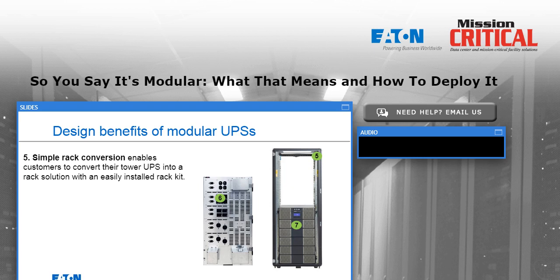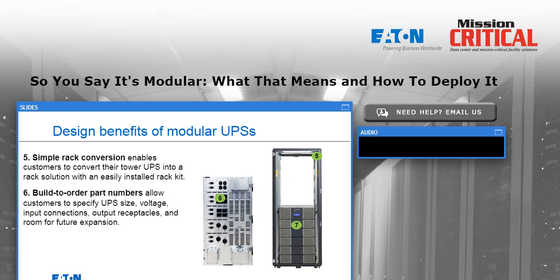If you're choosing to hardwire the output to this UPS, let's say to a panel on the wall or even an RPP, remote power panel, that can be done as well. But the receptacles give the ability to add and change things in the lineup of equipment cabinets without necessarily having to involve an electrician every time I bring in another load to put on that UPS.